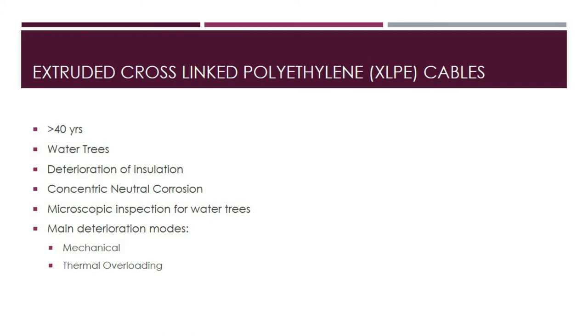Accelerated electrical testing of recovered cables can be used to identify the condition of cables of comparable design and vintage. A variety of organizations offer partial discharge testing and insulation power factor, or tan delta, measuring services for insulated cables. For low-voltage cables, the main deterioration modes are mechanical damage to insulation during installation, allowing water ingress, or thermal overloading.